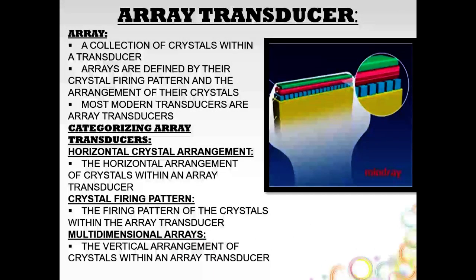Next, onto our array transducer. So an array, this just means that there's a collection of crystals within a transducer, so more than one crystal. You can see here these blue circles here, these are our crystals. Transducers have many crystals in them, and arrays are defined by how the crystals fire, so what the firing pattern, and also how the crystals are arranged. And most transducers today are these array type transducers.